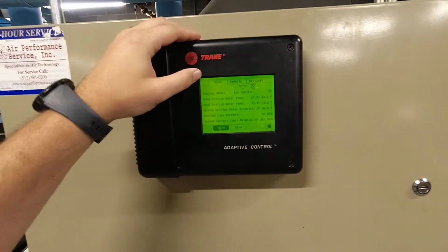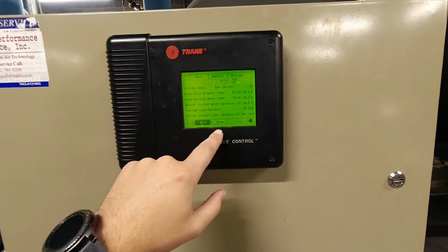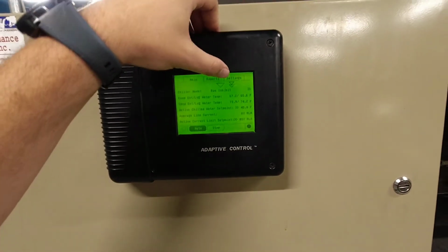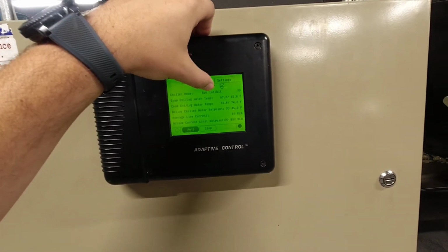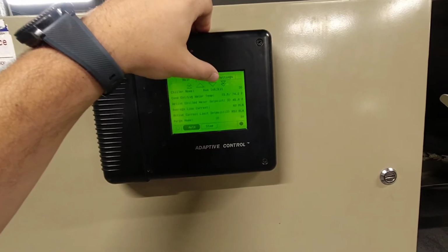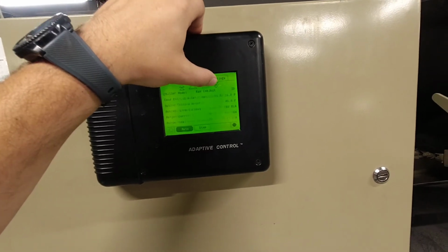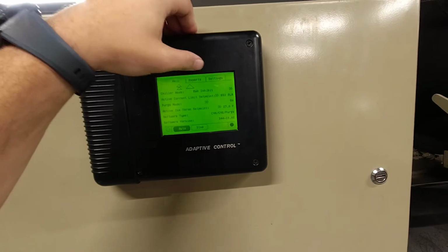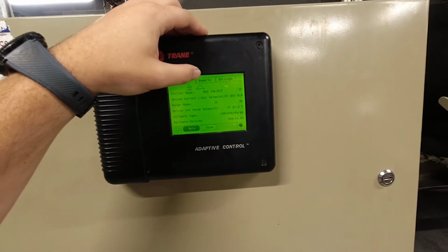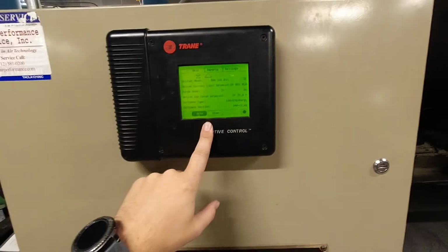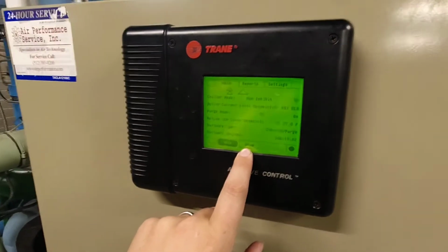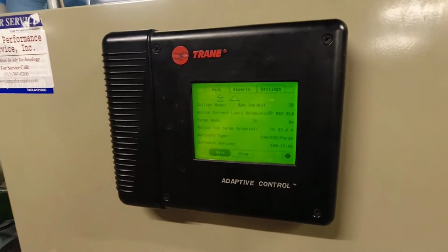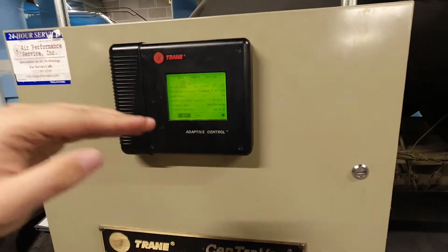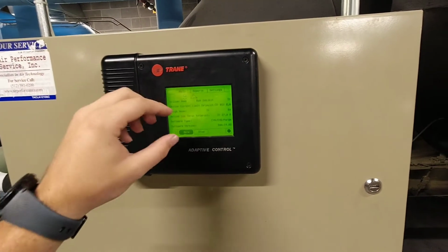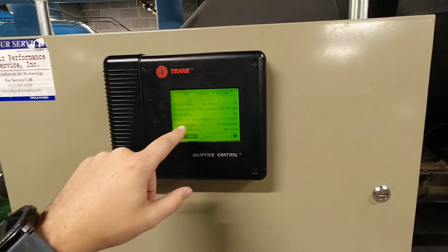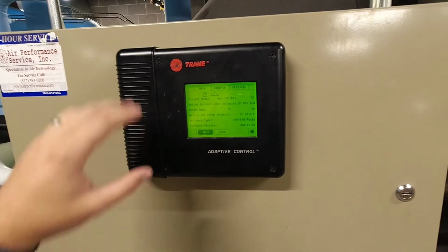It's going to have a real basic rundown on the main menu. You have auto and stop here on the front. You can either go down item by item with the single arrow, or if you hit the double arrow, you'll jump a whole menu set at a time. Whenever this chiller is running, if you hit stop, it's going to go into a cycle down stop. After you hit stop, it's going to ask you to hit stop again to confirm. There's a separate button for immediate shutdown.